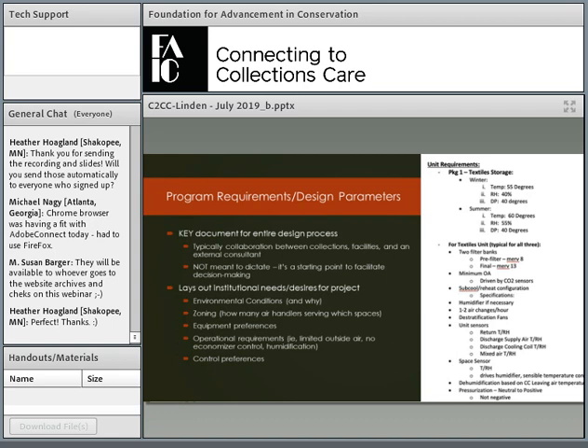If you have the same air handler serving your exhibition, collection storage, workspaces, and cafeteria, it's probably not a great idea for long-term preservation operability. Lay out what you expect that air handler to space relationship to be. We often recommend, as you'll see in the ASHRAE chapter, that you define zoning between different missions. Try to keep storage on its own zone. Exhibitions and workspaces for collections, occupied collection spaces, can go together. But public spaces with no collections, like the cafeteria, entryway, or a classroom, don't go on the same air handlers as the collections.